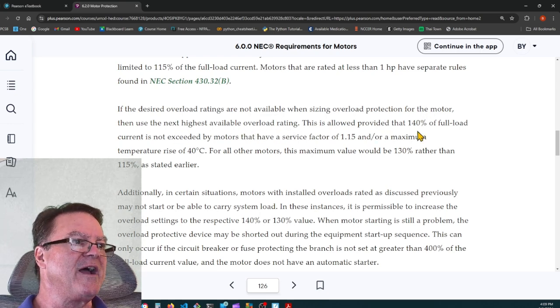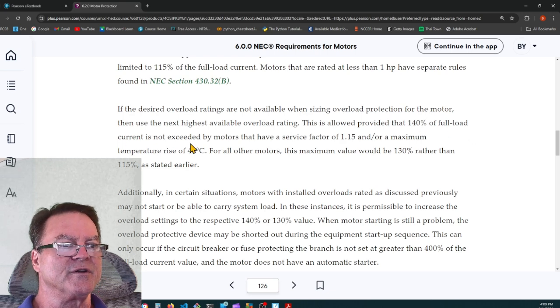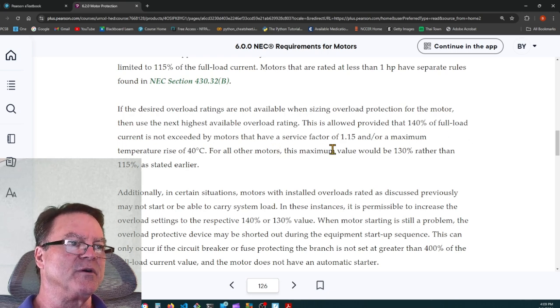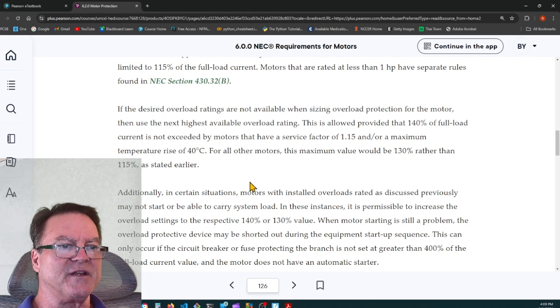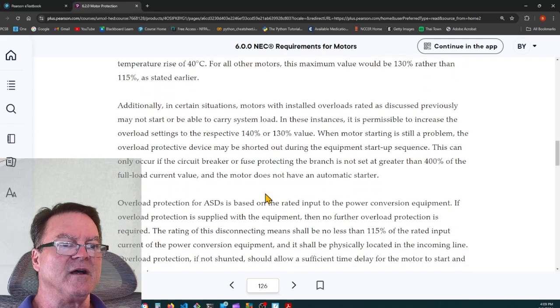This is allowed provided that 140% of the full load current is not exceeded by the motor that has a service factor of 1.15 and/or a temperature rise of 40 degrees Celsius. For all other motors, this maximum value will be 130% rather than 115% as stated earlier, if it's having trouble starting.